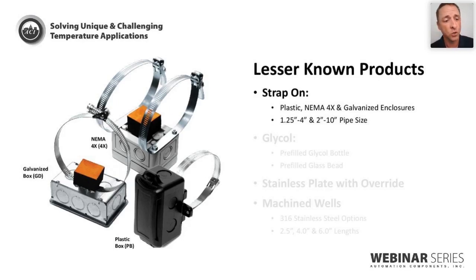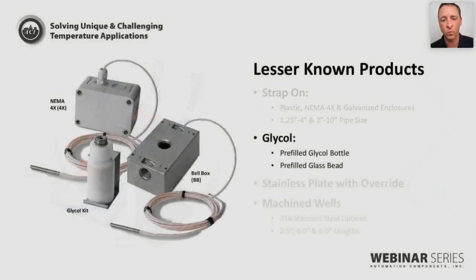Many of you may be familiar with our StrapOn type sensors, which are great for retrofit applications where you don't want to sink a new well into a pipe. But we do have the ability for these to measure pipes as small as 1 1/4 inches up to 10-inch in pipe size. And again, available in all of the different housings that you're familiar with.